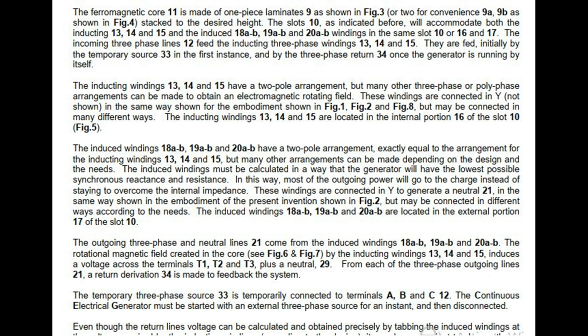needs. The induced windings must be calculated in a way that the generator will have the lowest possible synchronous reactance and resistance. In this way, most of the outgoing power will go to the charge instead of staying to overcome the internal impedance. These windings are connected in Y to generate a neutral 21, in the same way shown in the embodiment of the present invention shown in Fig 2, but may be connected in different ways according to the needs. The induced windings 18A, B, 19A, B and 20A, B are located in the external portion 17 of the slot 10. The outgoing three-phase and neutral lines 21 come from the induced windings 18A, B, 19A, B and 20A, B.